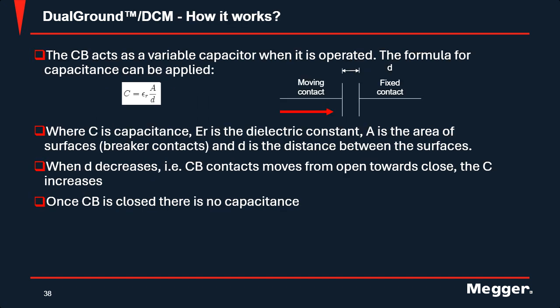So dynamic capacitance measurement relies on the natural capacitance of your circuit breaker to distinguish between open and closed state. A simple representation of the circuit breaker consists of your moving contact, which is right here, and then your stationary contact, separated by some type of medium, be that oil or SF6 gas. In a general sense, that circuit breaker is a capacitor. So C is your capacitance, E is your dielectric in this formula right here, A is the area of the surface of your breaker's contacts, and D is the distance between the two. When D decreases, so your distance between the two contacts decreases as in a closing operation, the contacts move from open towards closed, and C increases, so your capacitance increases. Once the breaker is closed, there's absolutely no capacitance.